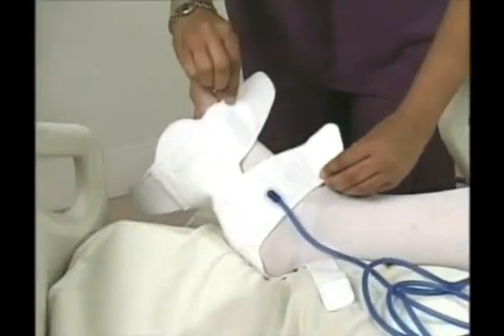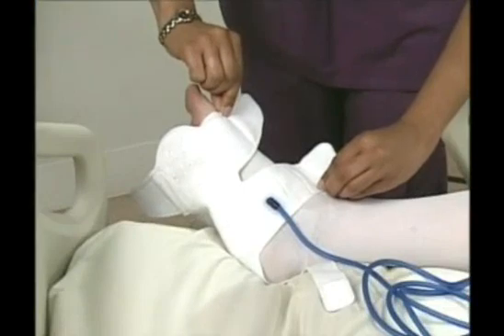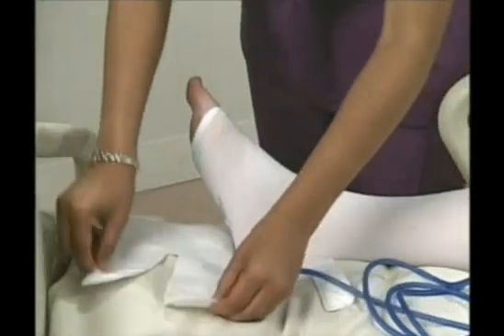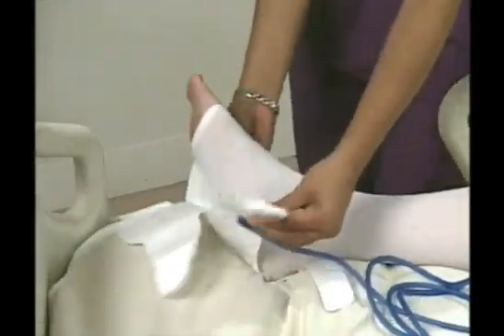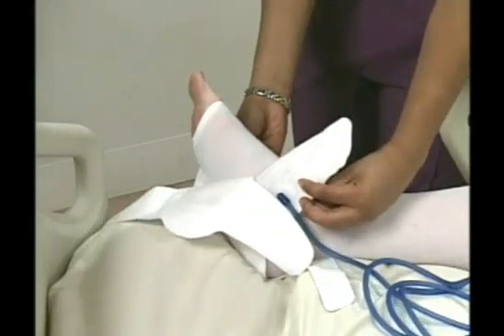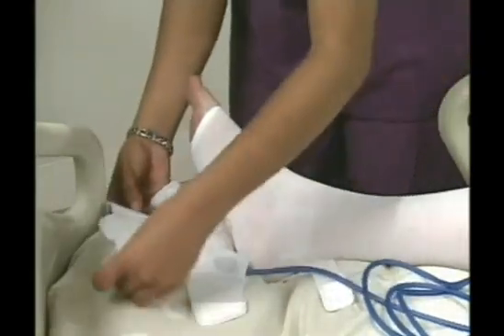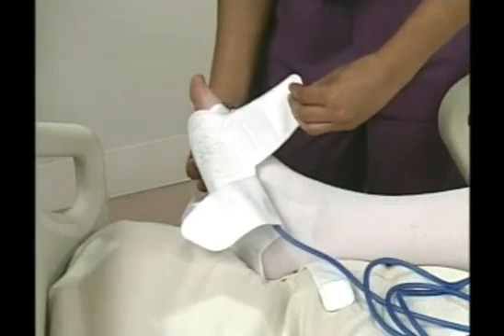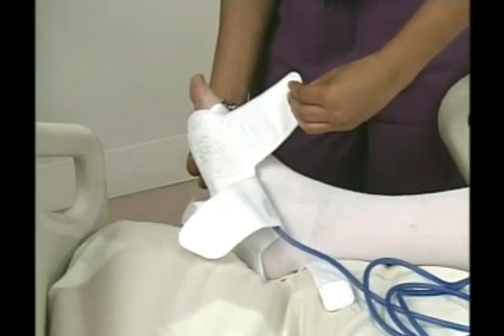Make certain that the smooth side of the sleeve is next to the patient's foot, with the tubes and fasteners located on the outside of the sleeve. Place the foot on the open sleeve with the heel positioned at the end with the longer tabs, and the toes at the end of the sleeve with the shorter tabs.